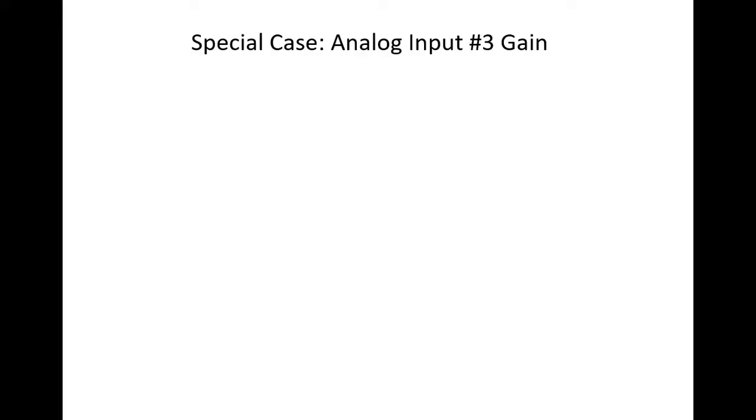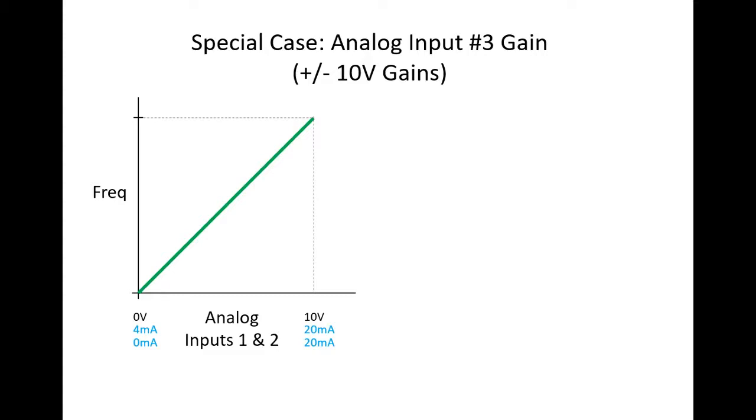Because analog input 3 can handle plus and minus 10 volts, it does gain a little differently than analog inputs 1 and 2. Gain and offset for inputs 1 and 2 are just the equation for a line. The gain is the slope and the offset is the y-intercept.